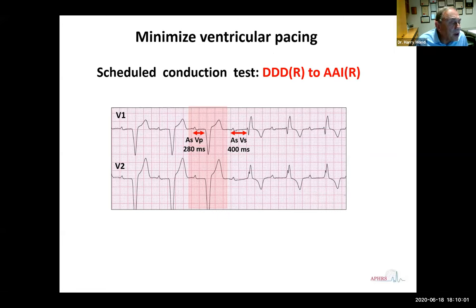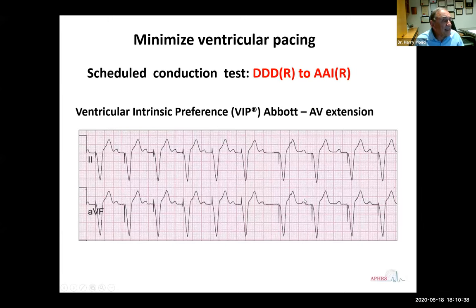What about the scheduled conduction tests? This is an example of where it goes from dual chamber DDDR to simple AAIR pacing. The pacemaker rhythm is shown with atrial sensing and ventricular pacing. It extends the AV delay here to 400 milliseconds, and there is a spontaneous QRS emerging. As a result of this, the pacemaker reverts back to AAI pacing. This is a success.